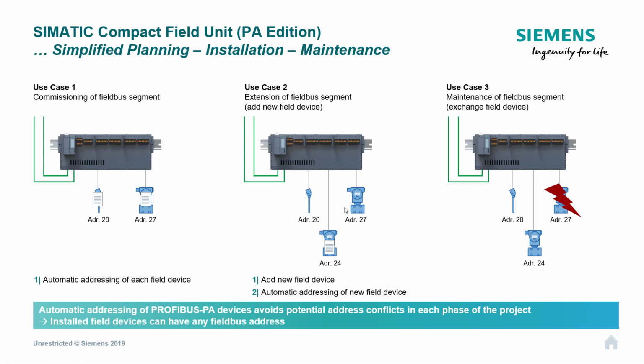Nice feature on the Compact Field Unit on PCS7, and when you're using it on PLCs with the GSDML, is it uses generic GSDs. So any manufacturer of instrumentation that supplies a device profile 3 and above is compatible with generic GSDs. So really, you don't need to put the manufacturer's GSD into your project. You shouldn't be tied down to that manufacturer. If you're not happy with the product that they're supplying, it allows you to move away and use something else as long as it's profile 3 or above.